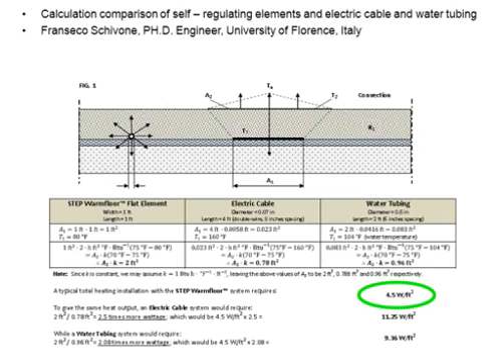And that kind of shows you here that Step Warmfloor, to provide a total heating system, really only needs around 4.5 watts per square foot. And if you look at the slides, it might be a little bit difficult for you guys to see on your computer, but an electric cable system is going to need 2.5 times that, or 11.25 watts per square foot, to achieve the same amount. And that's going to be energy savings right there.